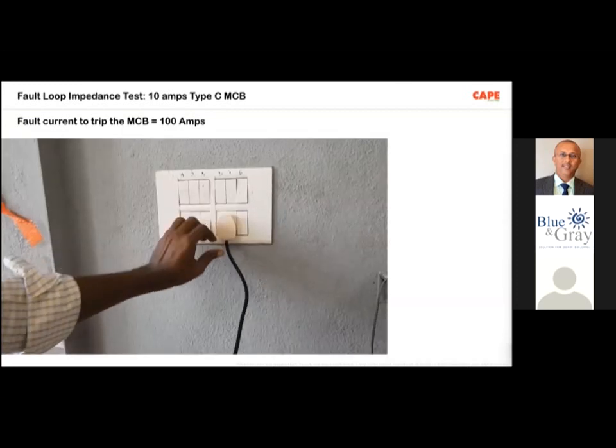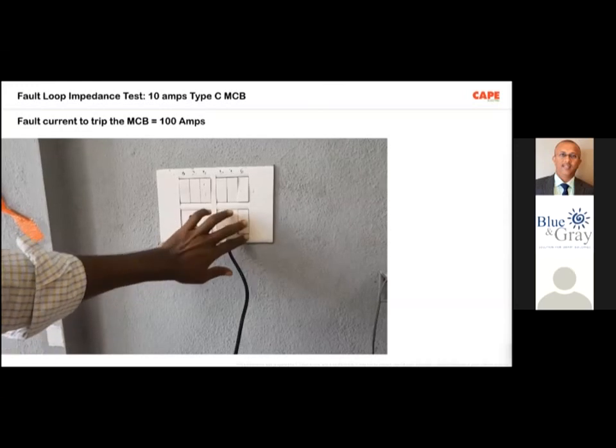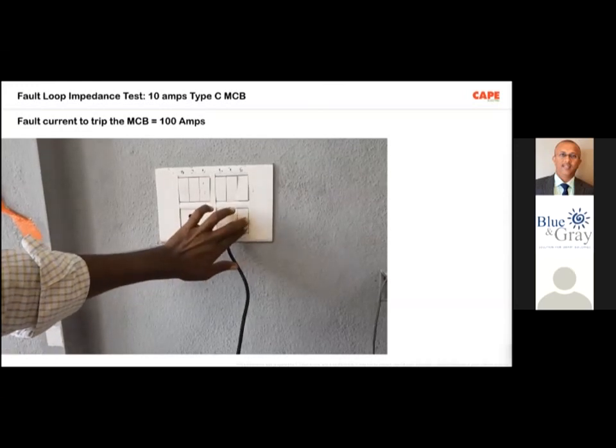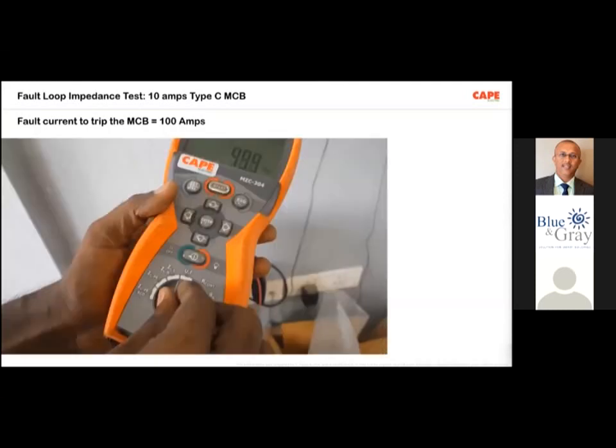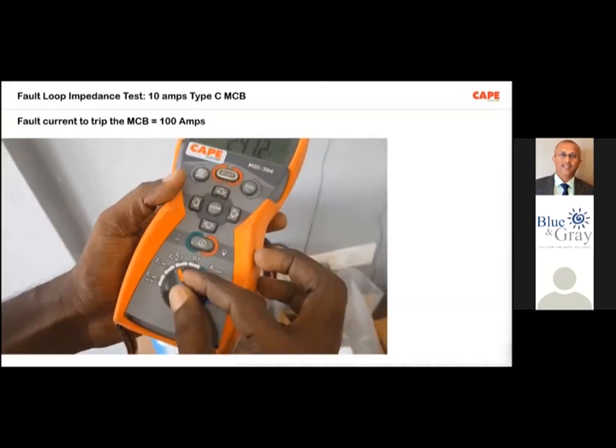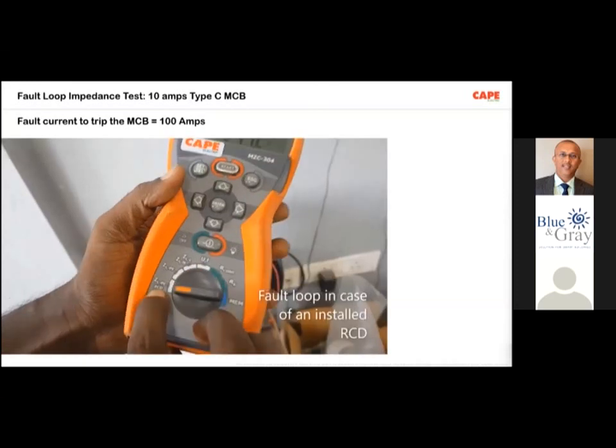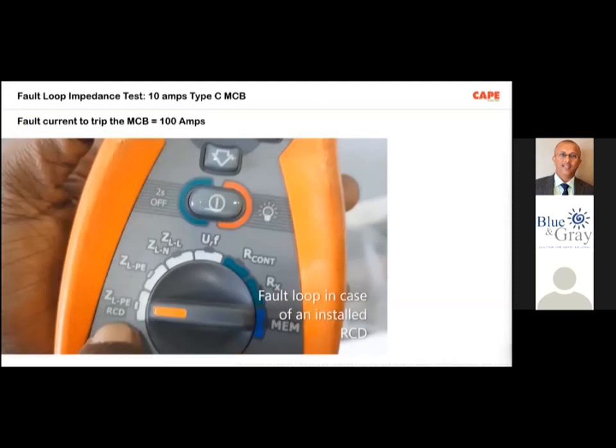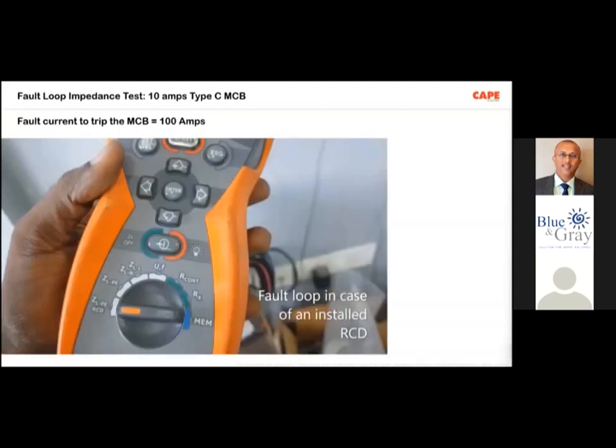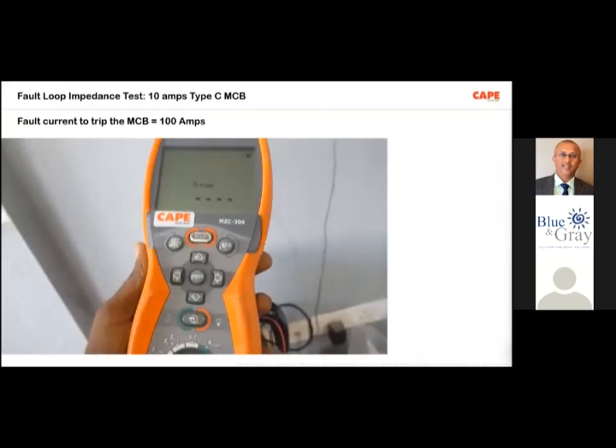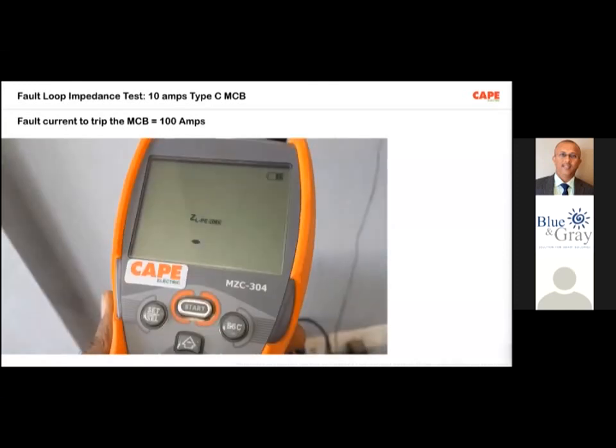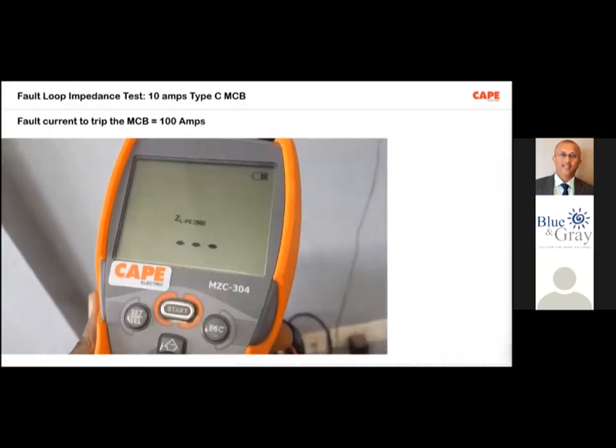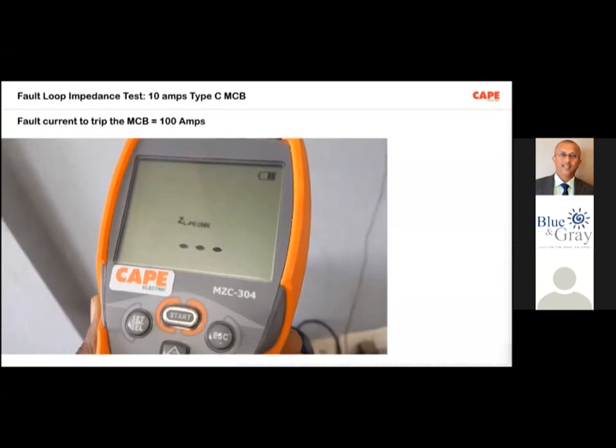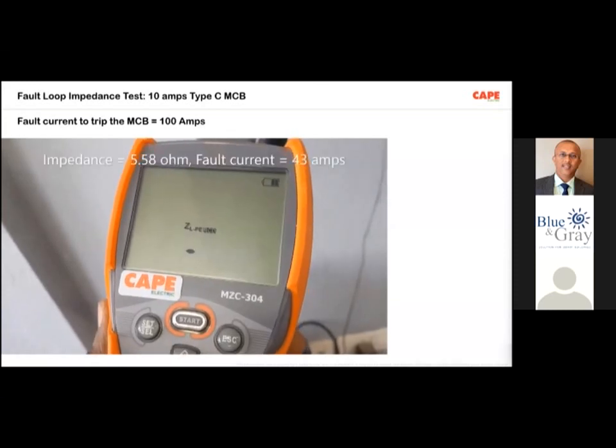Now I am just showing you a video. There is a plug, and this power is coming from a 10 amps type C MCB. You are aware that a type C MCB requires 10 times its rated current to create the tripping, and the meter has Z L-PE. Also, you see, we are using a very small meter to do this particular test because it's a final circuit, a 10 amp circuit. For a higher circuit, we need to have a more accurate meter. A bigger meter is required.